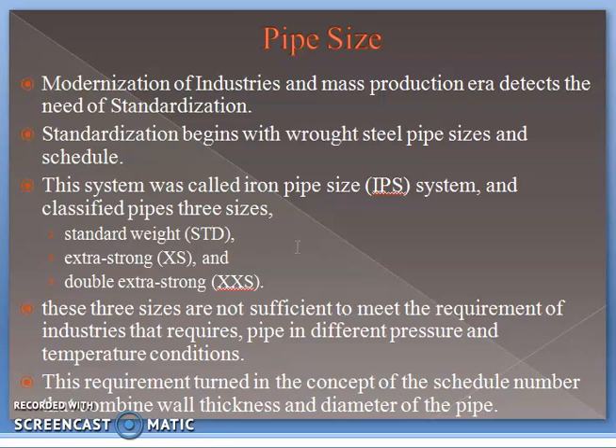The standardization begins with wrought steel pipe sizes and schedules. This system of standardization for wrought steel pipe is called the IPS system — Iron Pipe Size system. It classifies pipes in three sizes: first is standard weight, denoted as STD; next is extra strong, XS; and double extra strong, XXS.